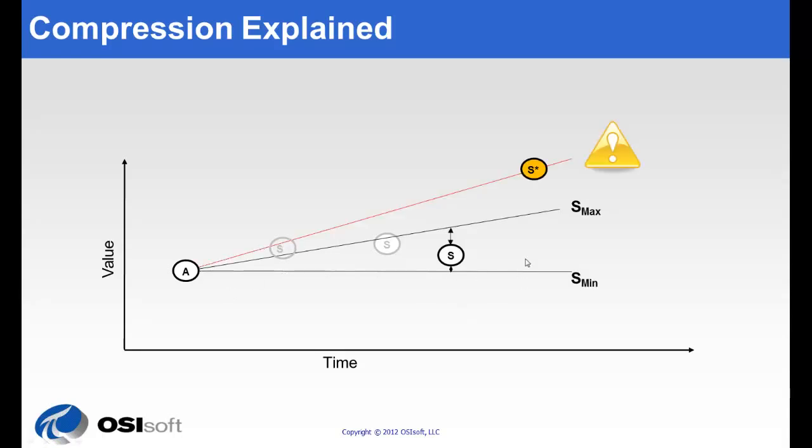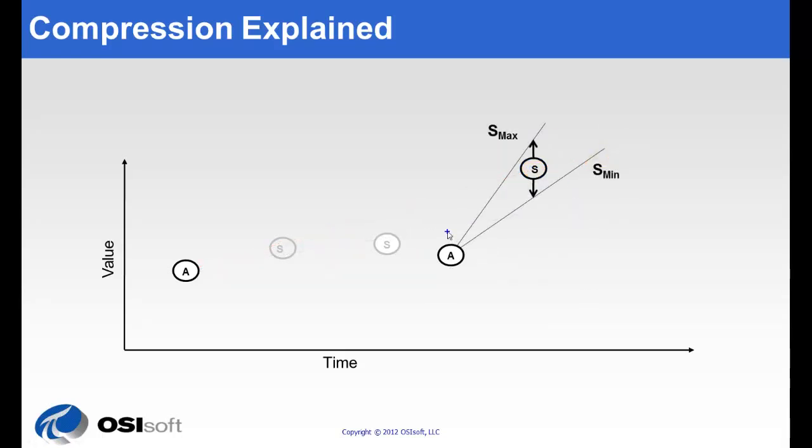When our next snapshot value comes in, we see that it's outside of our acceptable angle here. This means that we're going to keep this value, and this one will become the new snapshot value. We define a new archive value that will be written to the PI archives, and we start the whole process over again. We can also see that between any two archive values, the compression deviation defines a parallelogram that holds any data that happened in between those two archives.